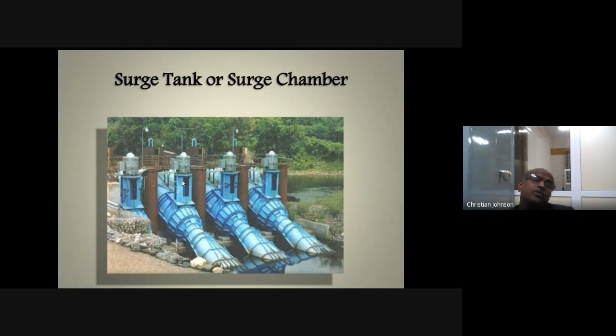In order to reduce the water hammer pressure at this critical portion, at this vulnerable point, some kind of well-like structure is provided. Sometimes it is excavated in the earth. In that case, it is called a surge chamber or surge shaft. Sometimes it is just above the ground, based on the topography of the land. If it is constructed above the surface, it is called a surge tank. If it is excavated below, it is called a surge shaft.